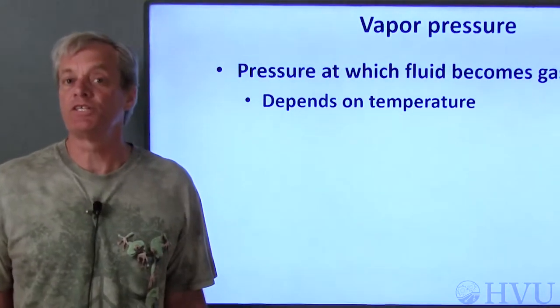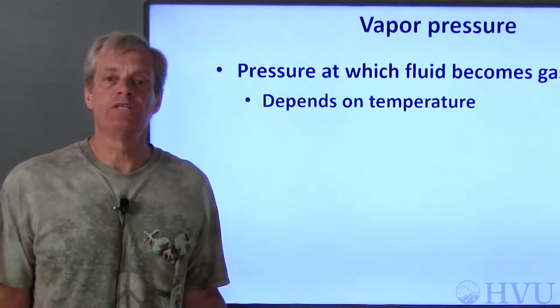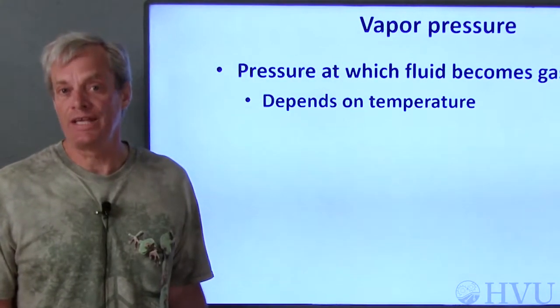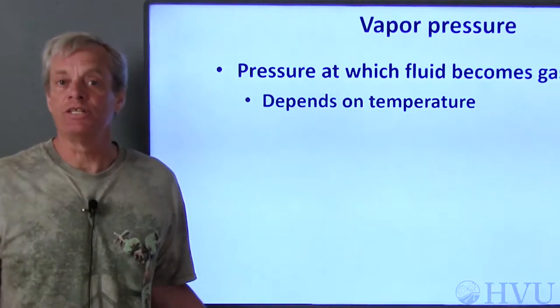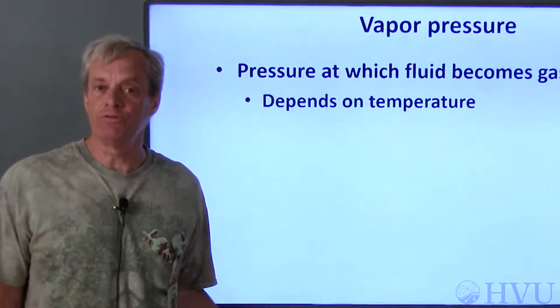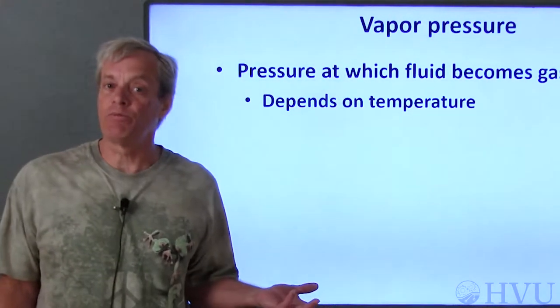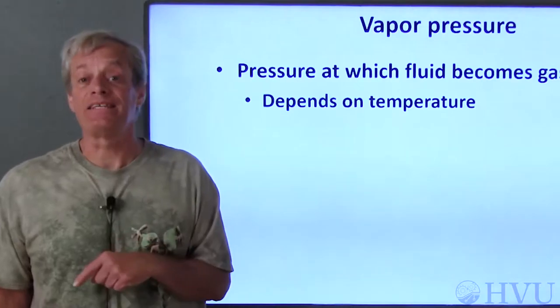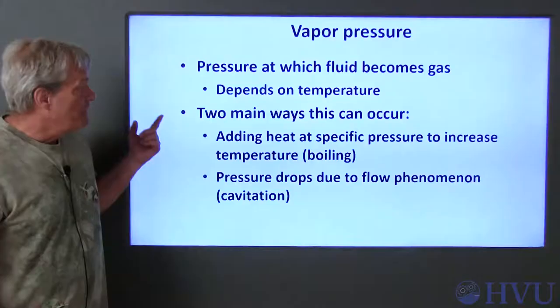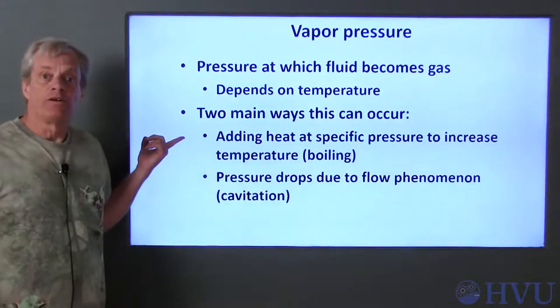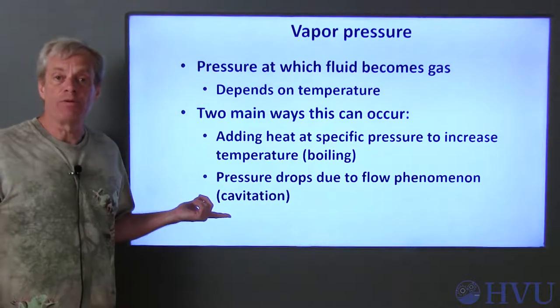Before talking about cavitation specifically, let's review the conditions under which fluids change to gas. This transition is governed by the vapor pressure in the fluid. If the fluid pressure is less than the vapor pressure at that temperature, the fluid turns into a gas. This means that there are a couple of different ways that we can turn a fluid into vapor.